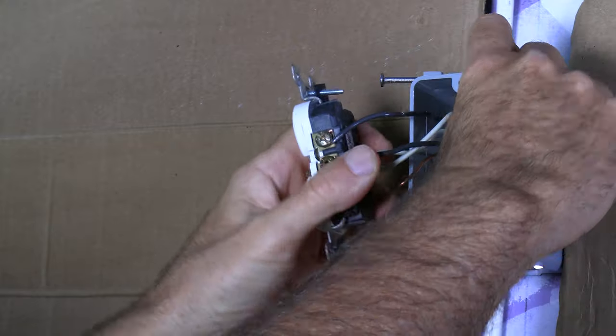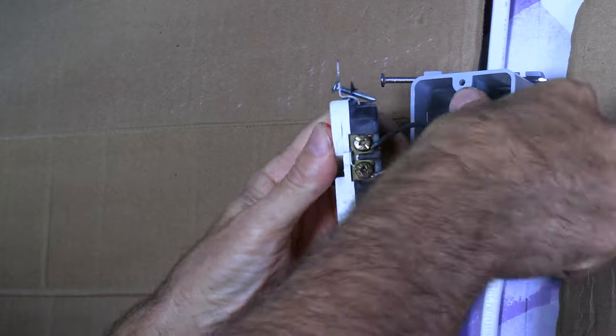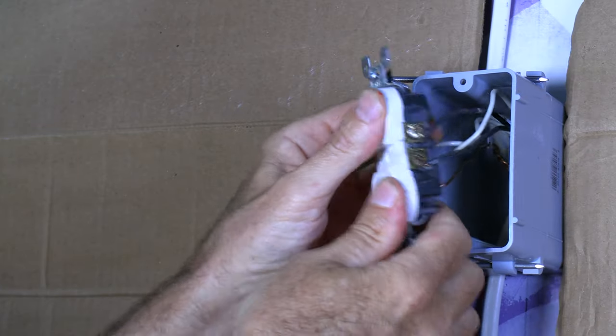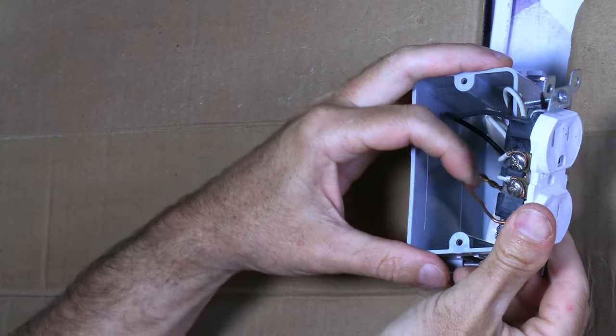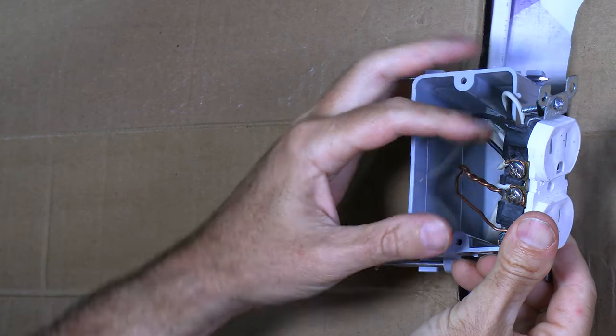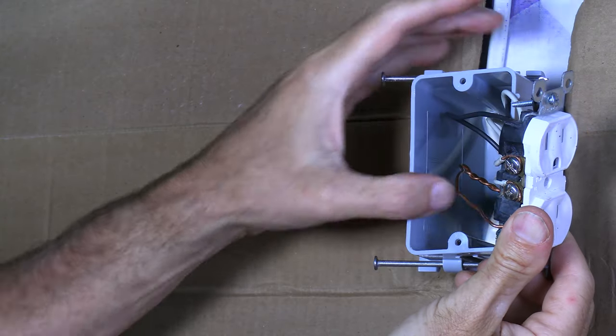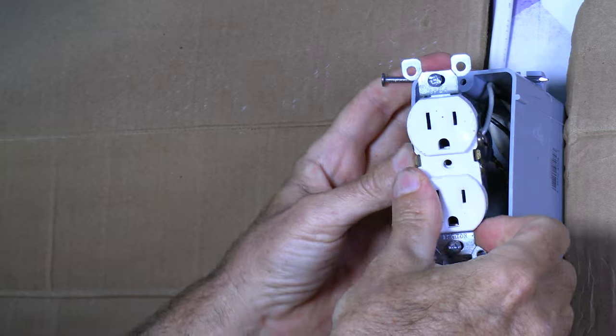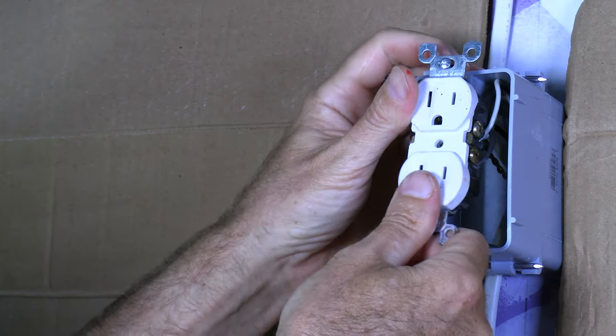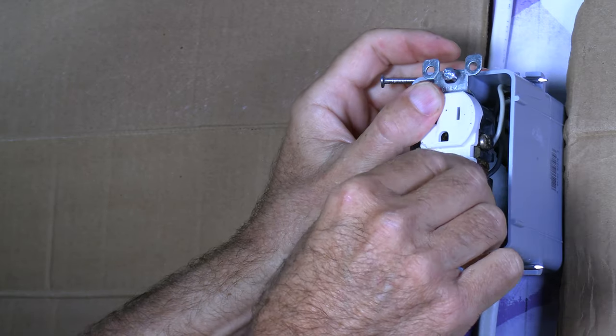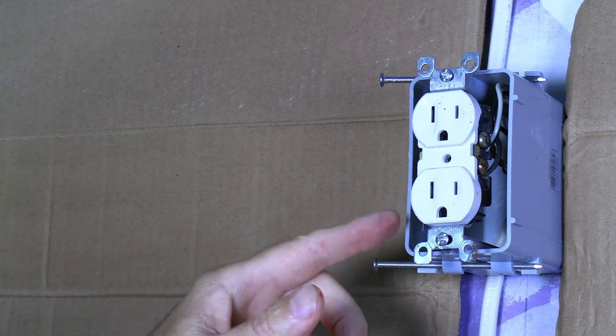So when you put these in here, sometimes I like to kind of take these wires and bend them up like this just to give more room so that I'm just not just shoving it all in there. And I kind of make sure that the ground wire here does not come across and touch the black side over here because that would be bad news. And you need to take note of where these wires are at and if there's any problems. All right. This is a little harder to do with 12 gauge wire, but it's the same principle. All right. And go ahead and get your screws started and then screw that puppy on down.